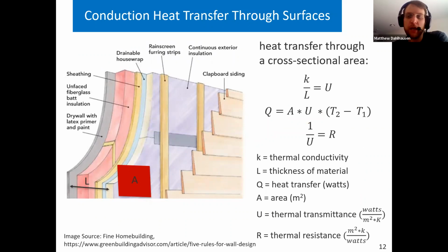If a building had no heat transfer and no people or equipment inside, the air temperature would stay the same. Conduction heat transfer is one of the main sources of heating and cooling loads. Heat transfer is determined by the thermal conductivity of a material, the thickness of the material, the surface area, and the temperature difference across the material. Temperatures and surface area are determined by the climate and the building. The thermal transmittance, or its inverse, thermal resistance, is a property that can be controlled and is specified in building codes. Building energy code stipulates maximum U values for roofs, walls, windows, and floors, often broken out by climate zone. Insulation is more important for a building in Anchorage, Alaska than it is in Los Angeles, California.